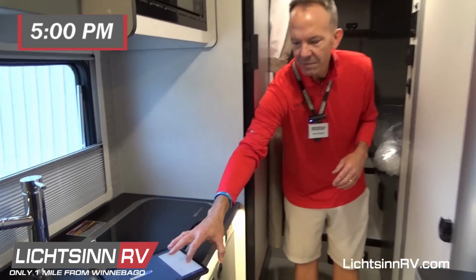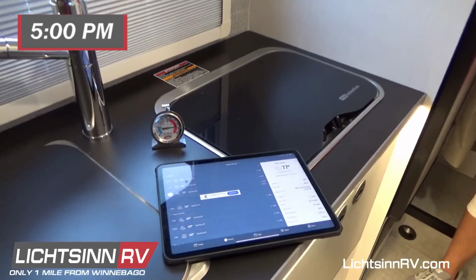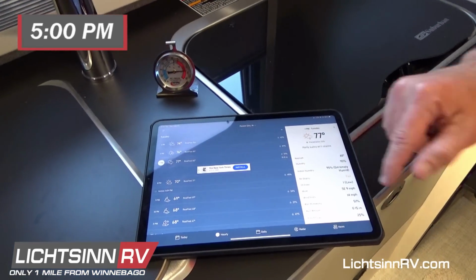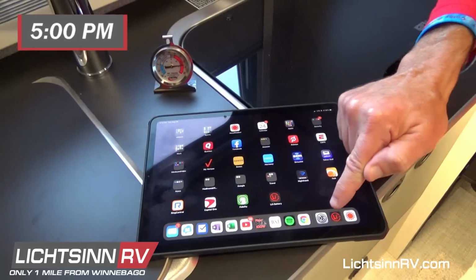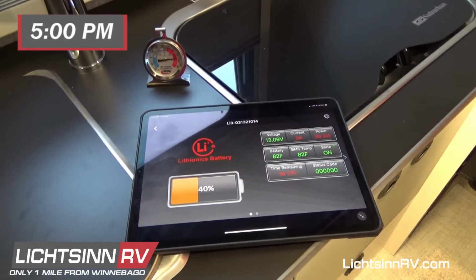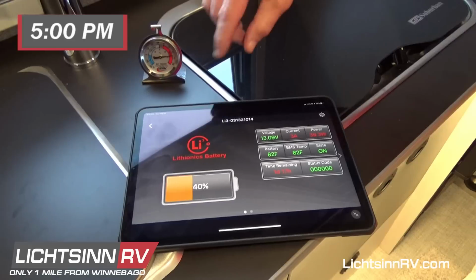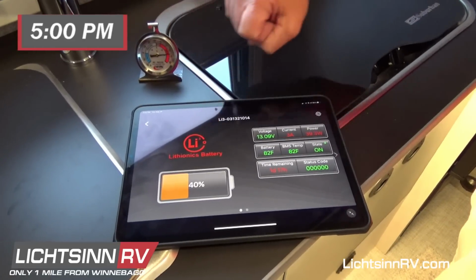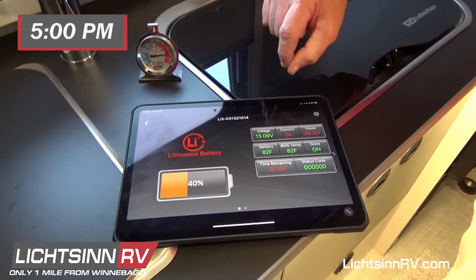Okay, so welcome back. We are 8 hours into our AC runtime test on the all-new Winnebago EKKO. It's just after 5 o'clock Central Time here in Forest City, about 5:10. Outdoor heat index is around 82 degrees. It's 95% humidity, and let me use my cheat sheet here, 76 degree dew point. So really have had a muggy day, and as we slide over and check the status of the Lithionics system, we are now in the orange section, which is 40%. We have 13.09 volts.